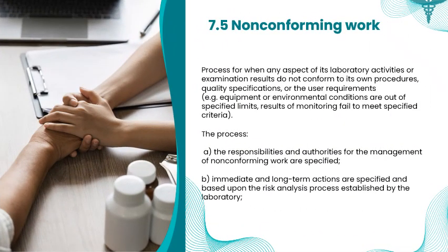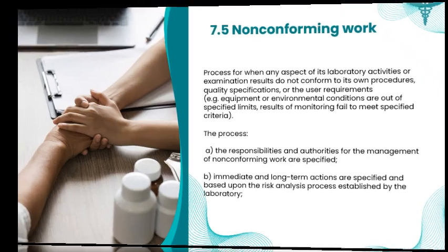Non-conforming work. The laboratory shall establish and maintain a documented process for managing situations where any aspect of laboratory activities or examination results fails to conform to its own procedures, defined quality specifications, or user requirements, for example, equipment or environmental conditions outside specified limits, or monitoring results not meeting required criteria. The process shall ensure that responsibilities and authorities for the management of non-conforming work are clearly defined and documented. Immediate and long-term actions are determined and implemented, based on a risk analysis process established by the laboratory, to minimize patient safety risks and prevent recurrence.